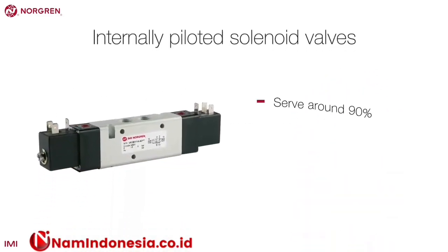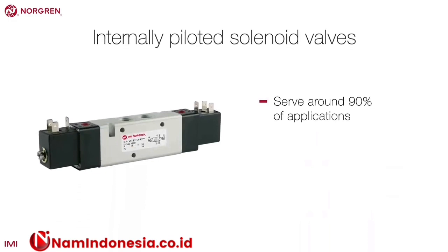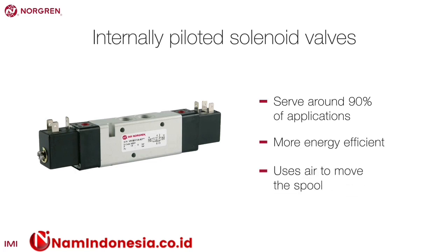Internally piloted solenoid valves serve around 90% of applications. This is by far the most common type of solenoid valve and is much more energy efficient. They use air to move the spool across, changing the position of the valve.